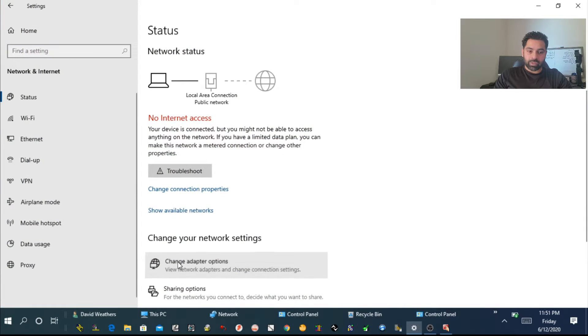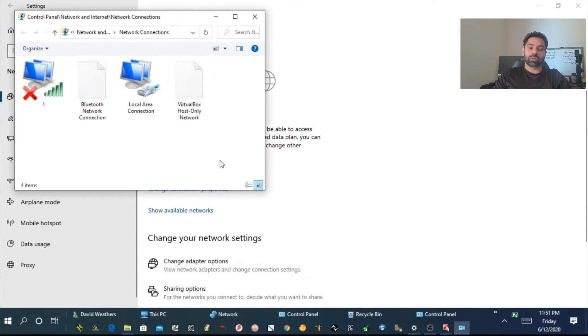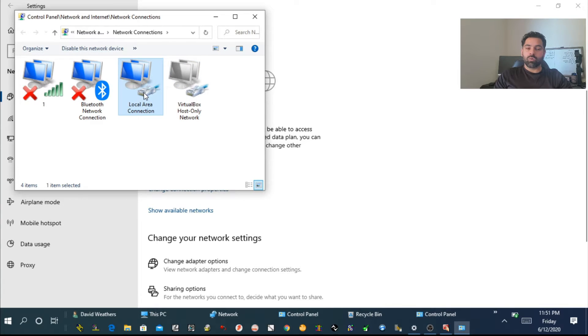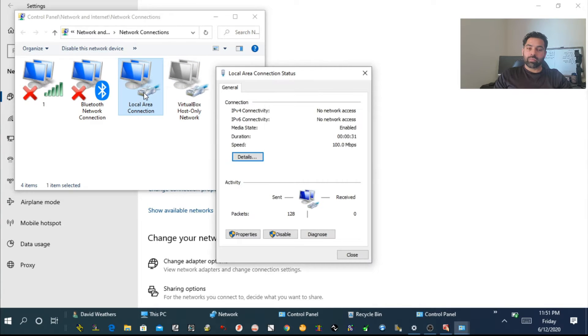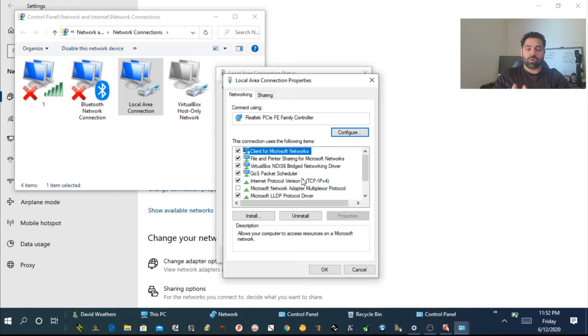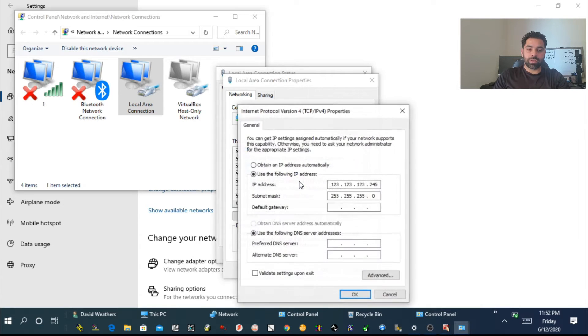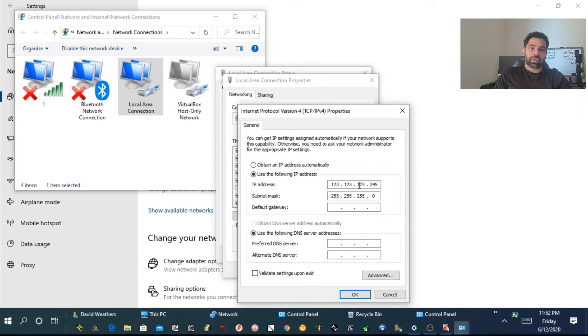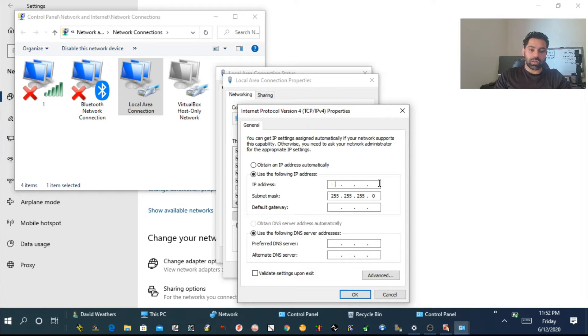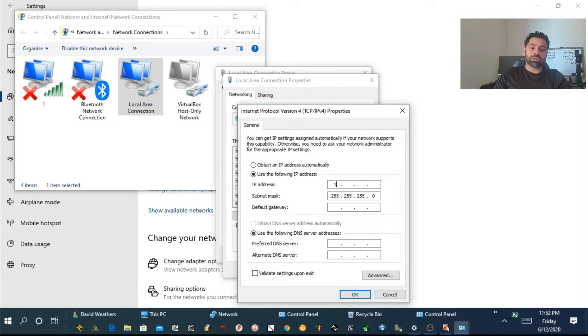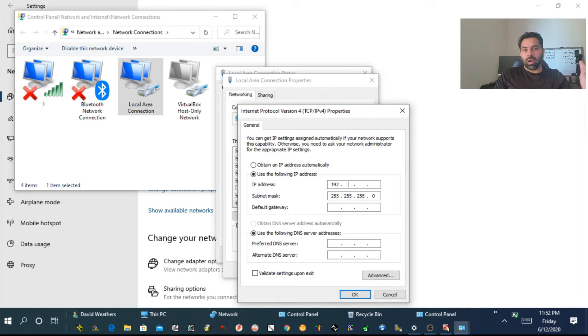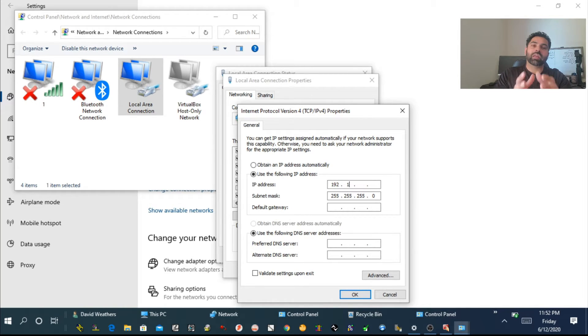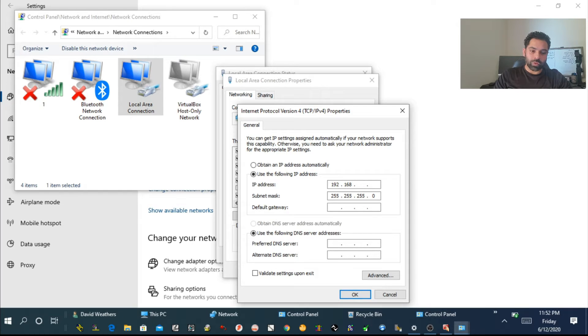Go to your local area network, change the network adapter settings, click on local area network, select Properties. For network protocol IPv4, we're going to put an IP address from the same group. My PLC IP address is 192.168.1.30.